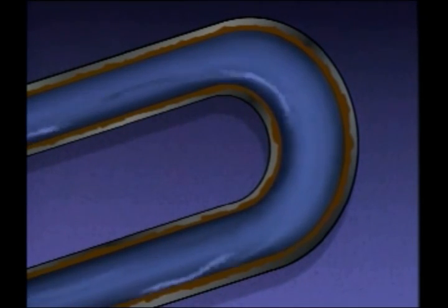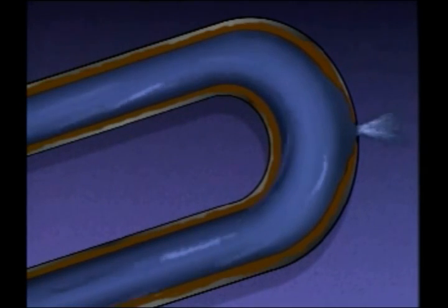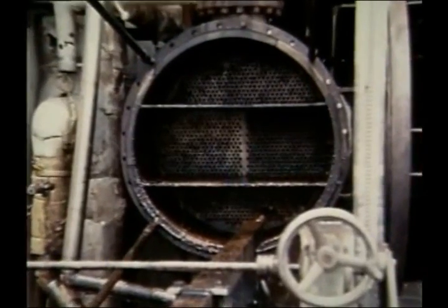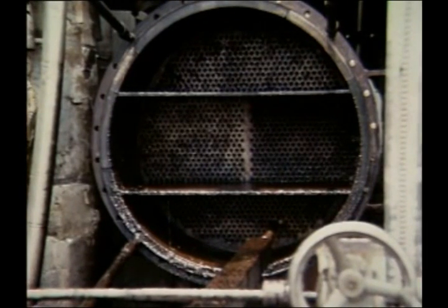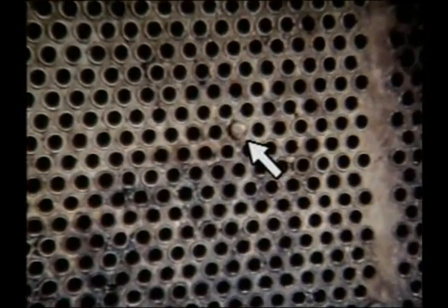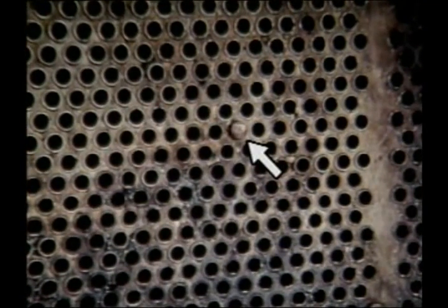Weakened tube metal from corrosion may lead to tube leakage. If a tube leaks, the heat transfer process is affected, but an even more serious problem is the contamination of fluids flowing through the heat exchanger. When leaks occur, the heat exchanger is usually shut down for inspection and repair. If only a few tubes are leaking, they could be plugged and the heat exchanger put back into service at reduced efficiency. If there are a lot of tubes leaking, more extensive repair work may need to be done.